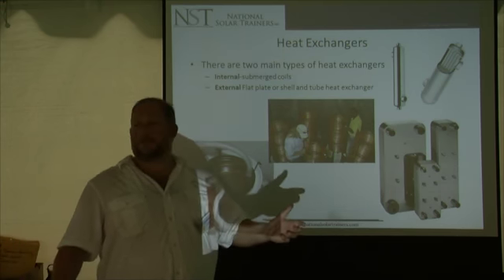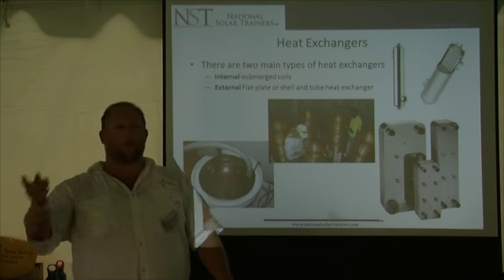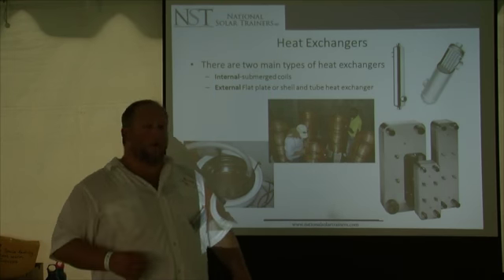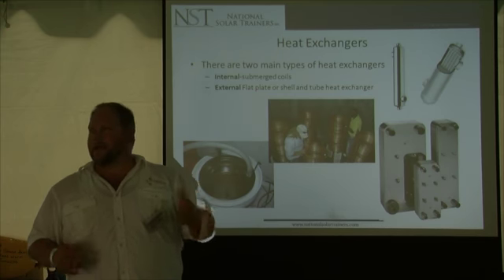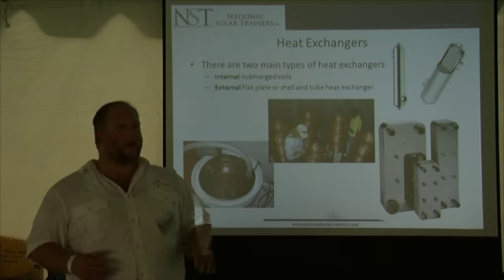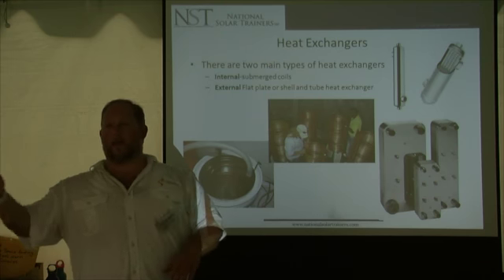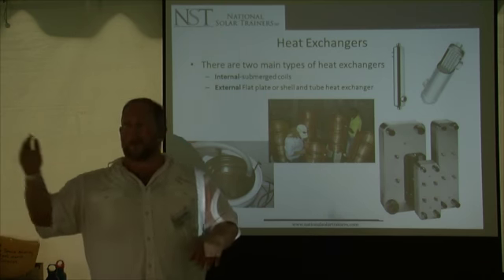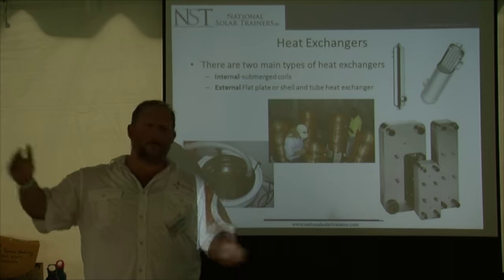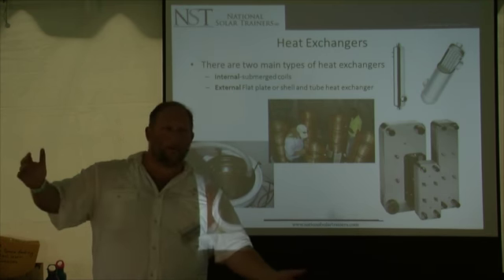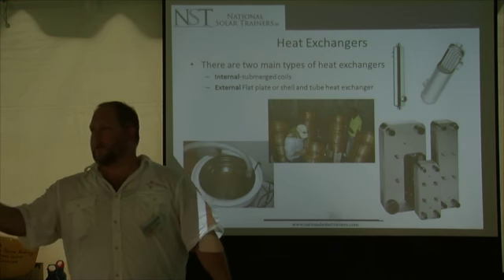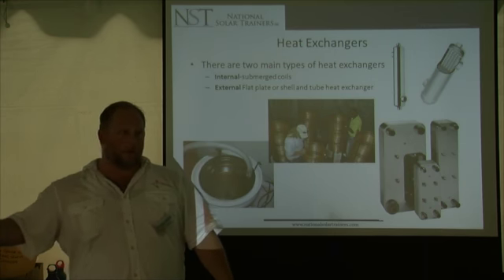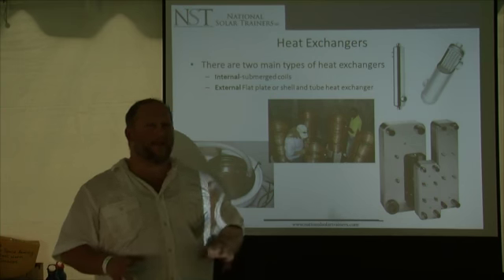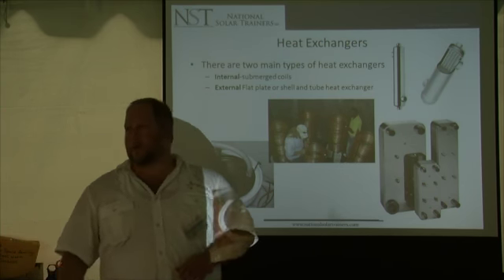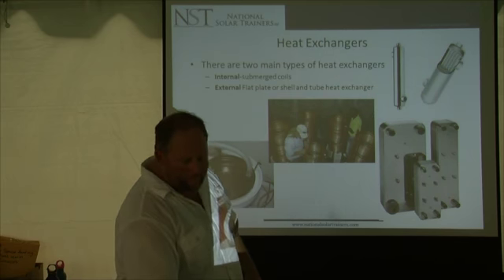Somebody has a deionizer in their house, and they're running their potable water through a copper coil. Well, it's deionized water, and deionized water has very low ion content. Copper has a high ion content. And what happens with a high ion to low ion? The ions come out of the copper and cause the copper to erode and corrode quicker. So be careful about using deionized water in your copper coils. It's going to increase the rate of corrosion.